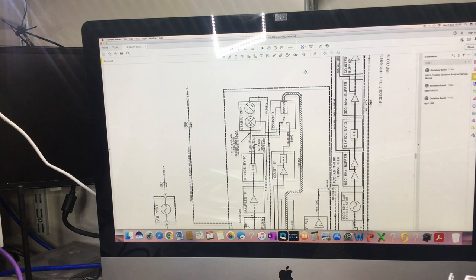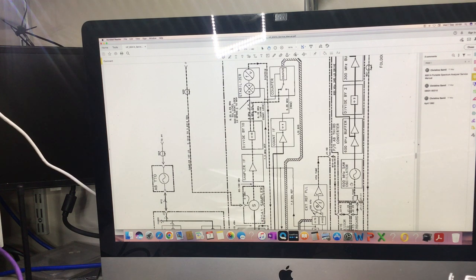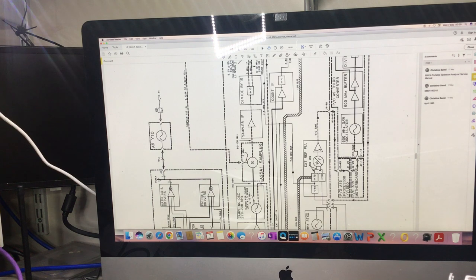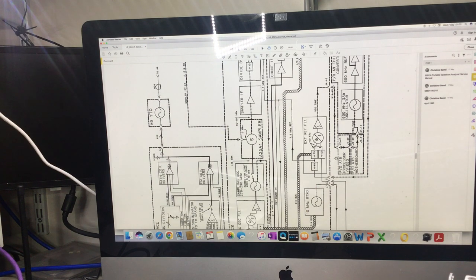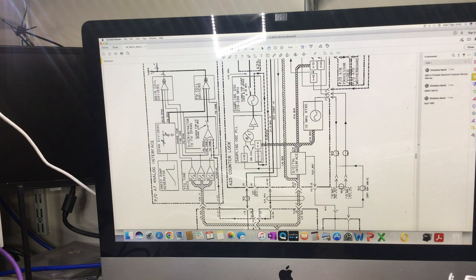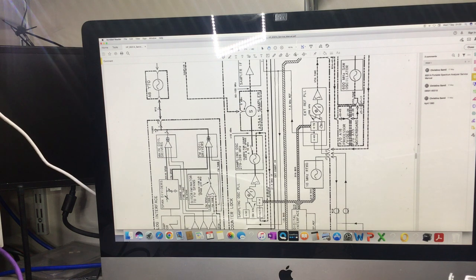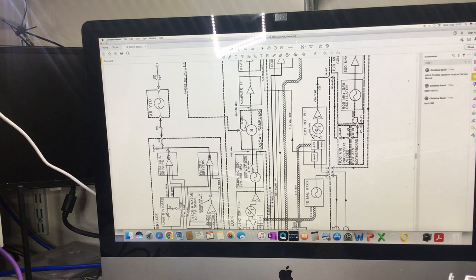Because the third converter here shows the 600 MHz oscillator, and that then has its control volts, J3, there we are, look, VTO tune. This possibly could be looked at next, to see where the tune voltage moves about, because what we could do is remove the 10 megs reference oscillator, which is coming in from down here. The 10 megahertz is coming in to this, divide by 100. If we remove that, this voltage will probably change quite wildly, because it's lost its reference. It's then trying to influence this frequency.